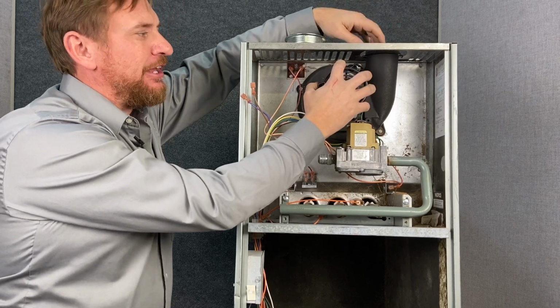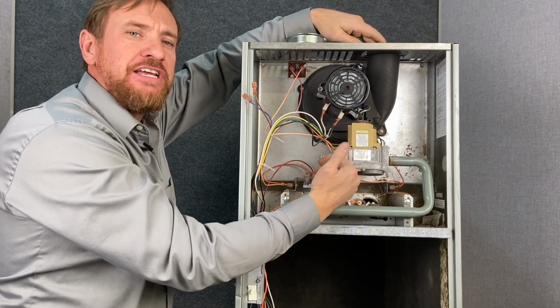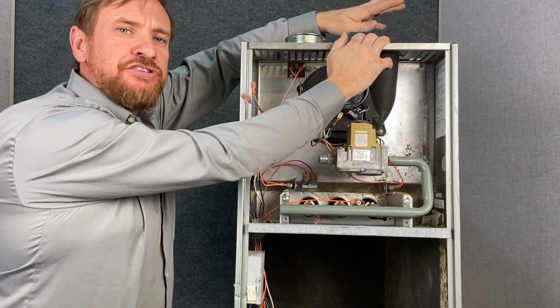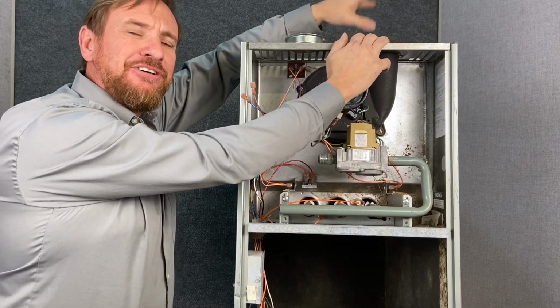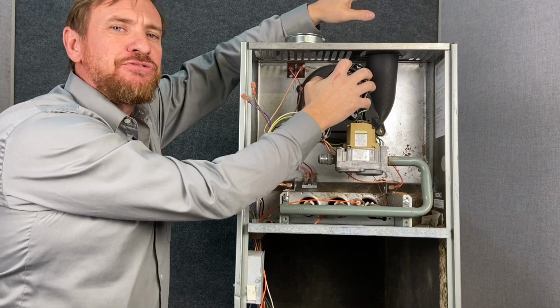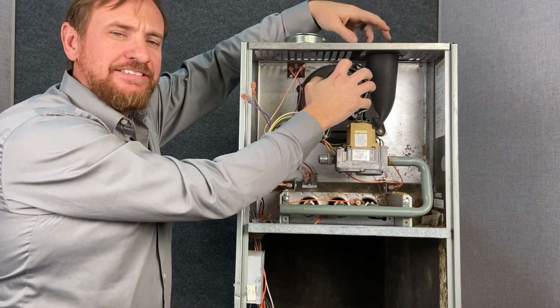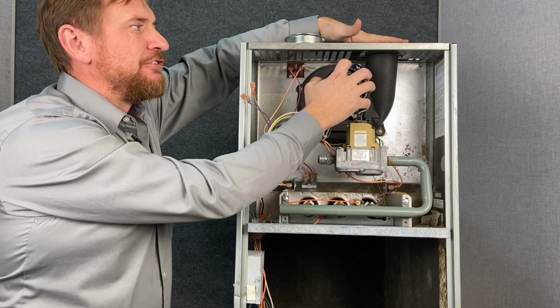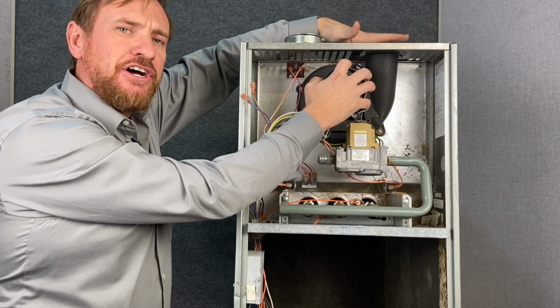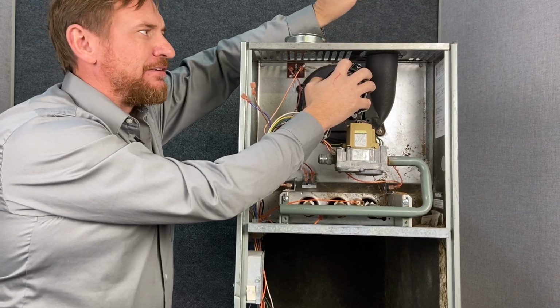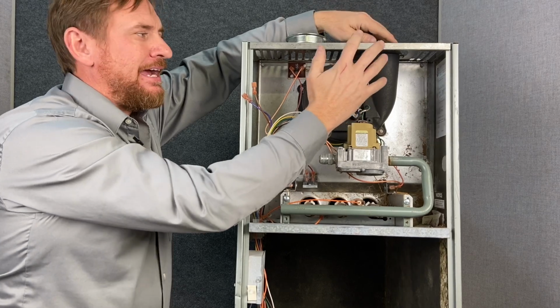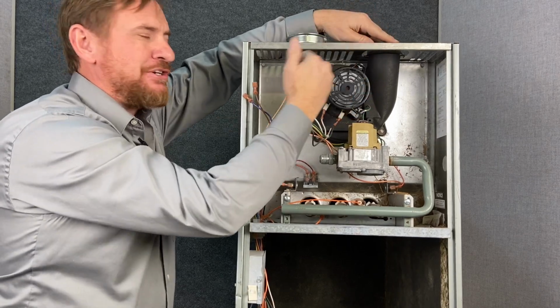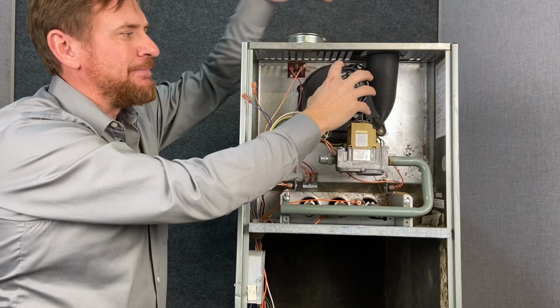This inducer motor helps pull, it does pull the draft through the heat exchanger. It helps start the draft, but it does not pressurize that flue pipe. It's still natural draft and relies on natural convection, the heat being less dense rising up. A lot of people think this is forcing the exhaust at the flue, and that's not true. I've seen before a bird nest completely stopping up the flue pipe, and this not have enough back pressure to set off that pressure switch. So that's important to keep in mind.